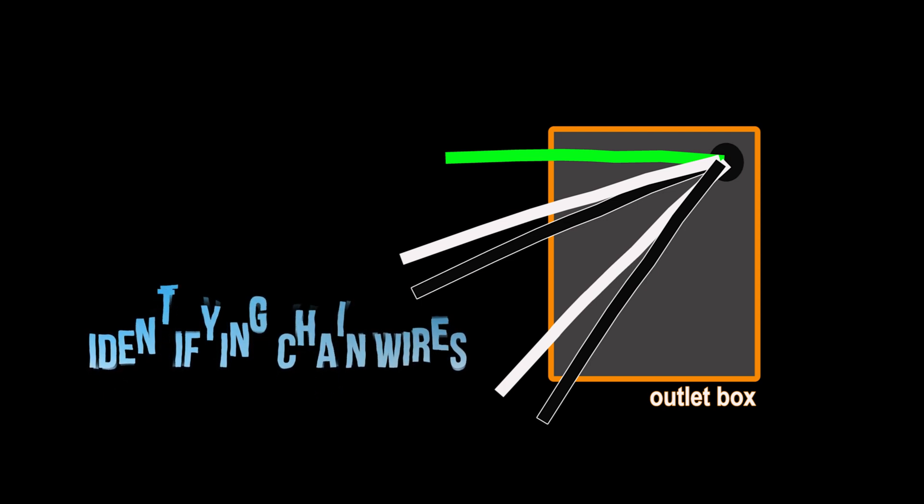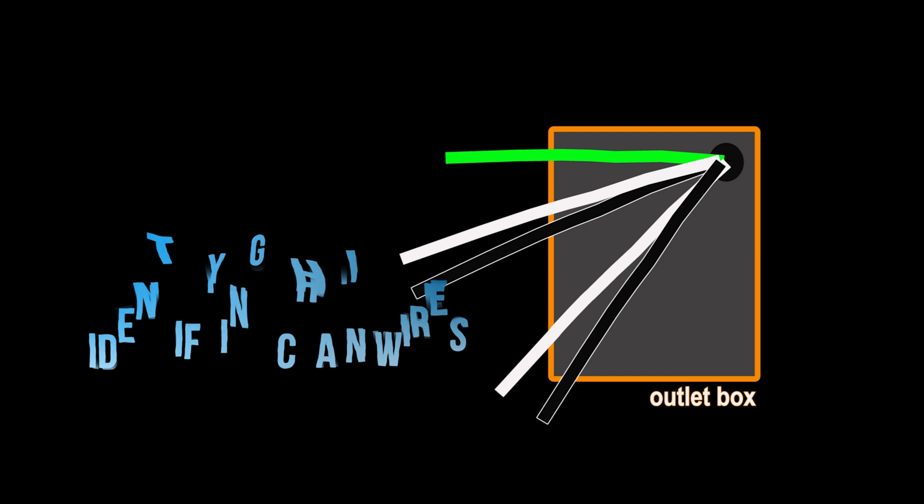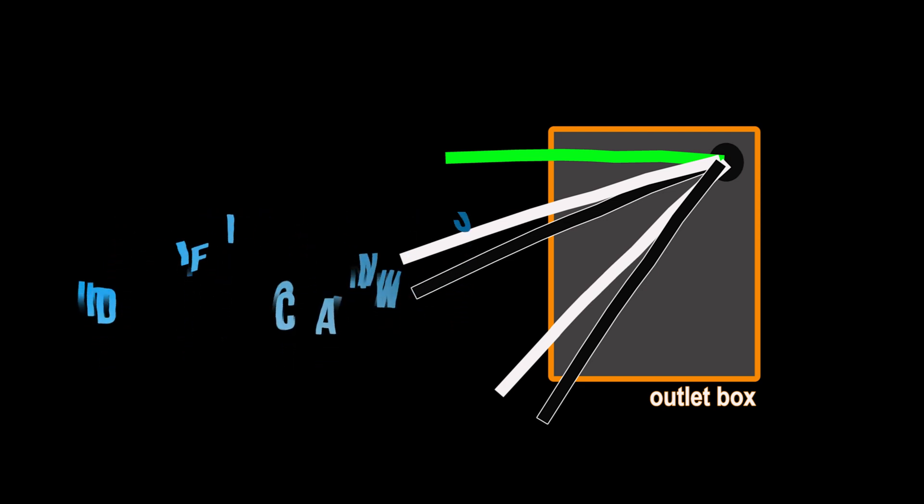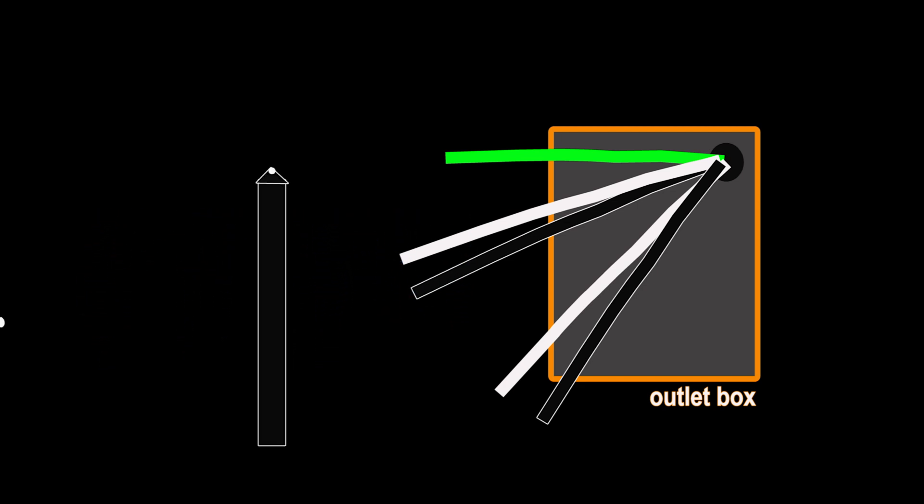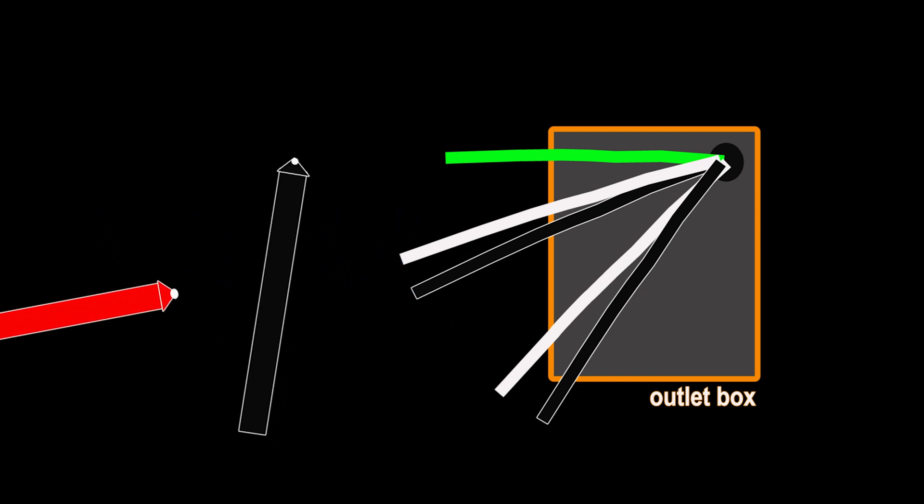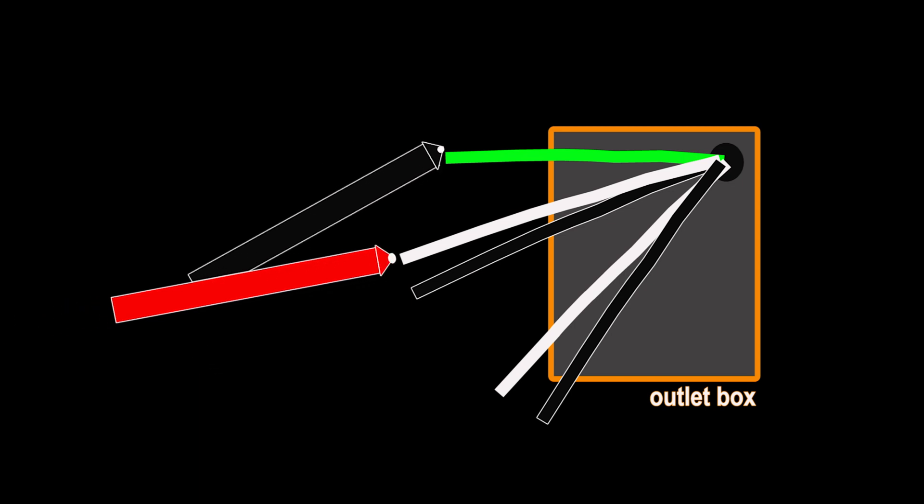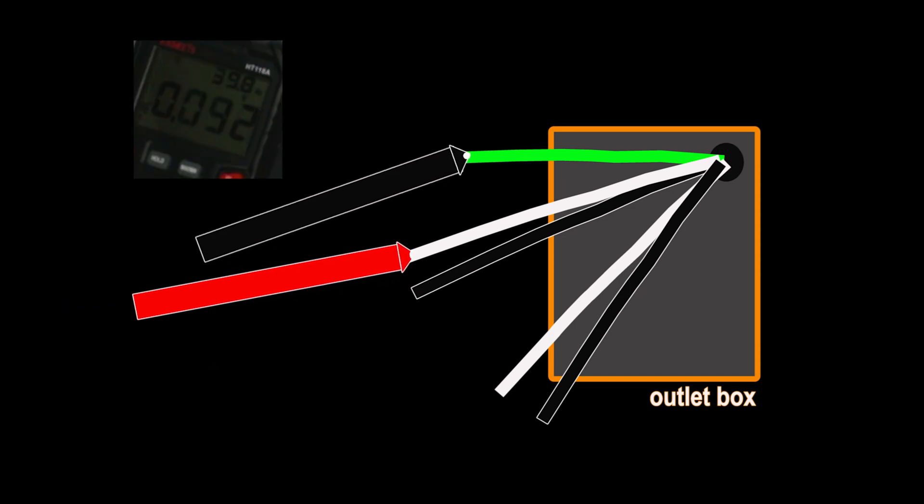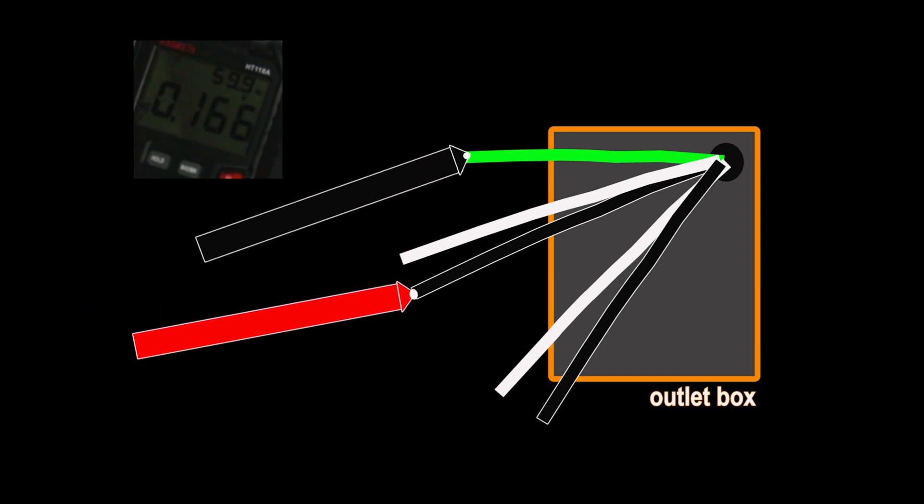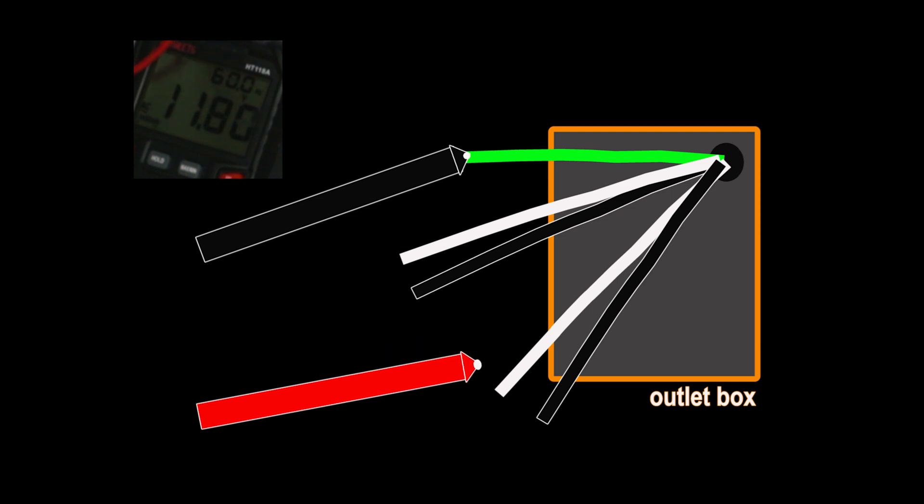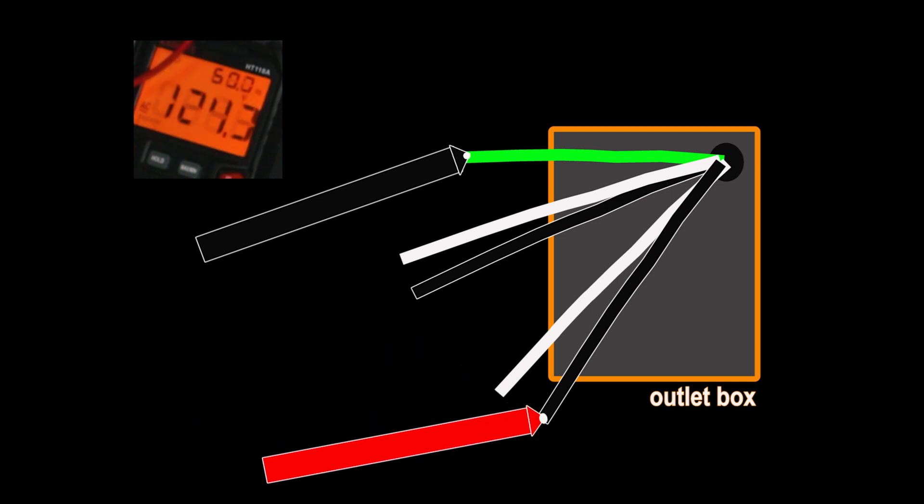If all five wires are unplugged and spidered out with the breaker on, with the black multimeter lead on the ground, only one of the possible four combinations will result in a reading. This is your main hot.